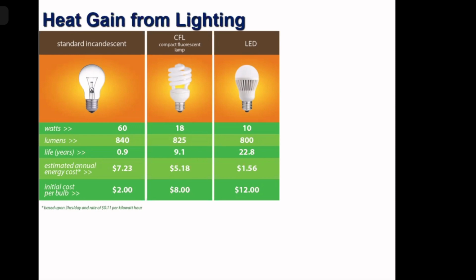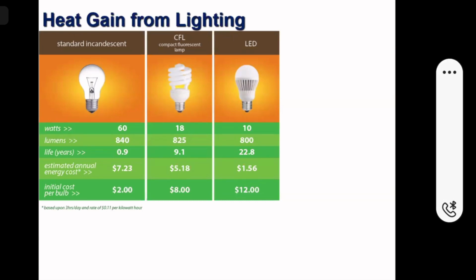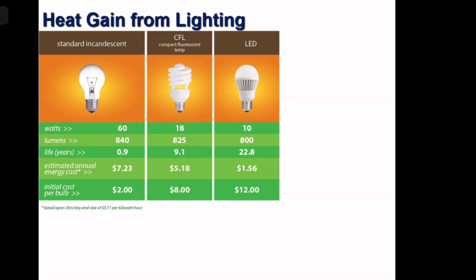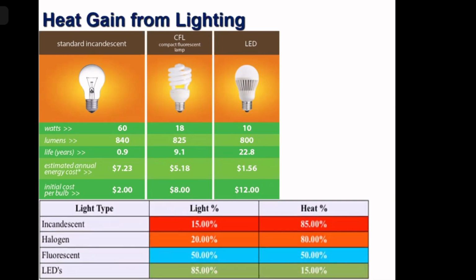And because LED lights produce more lumens per watt, there will be much less heat in the AC space because of lighting if you use LED light. So now switch everything to LED light. With incandescent light, you get only 15% light out of the total energy spent, and 80 to 85% comes as heat. Halogen is this, fluorescent is this, and LED is this.